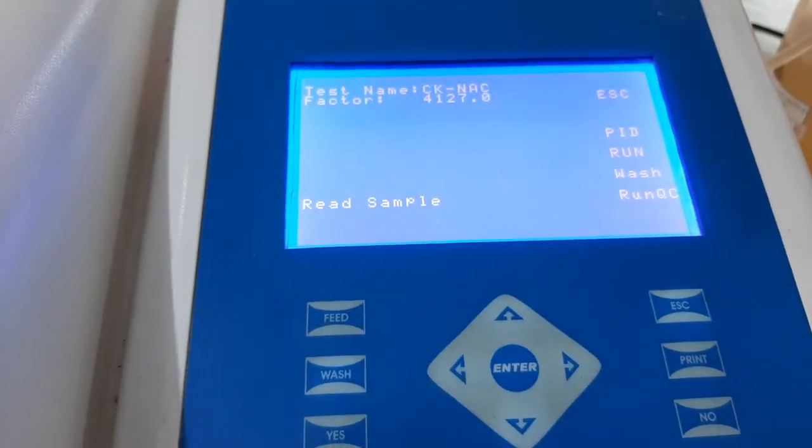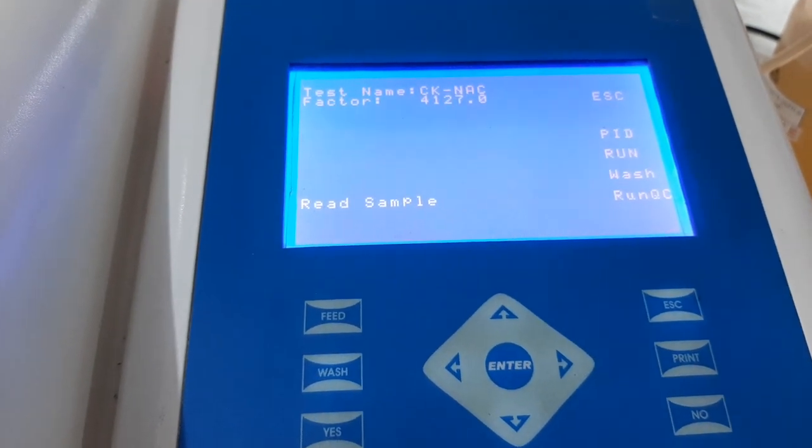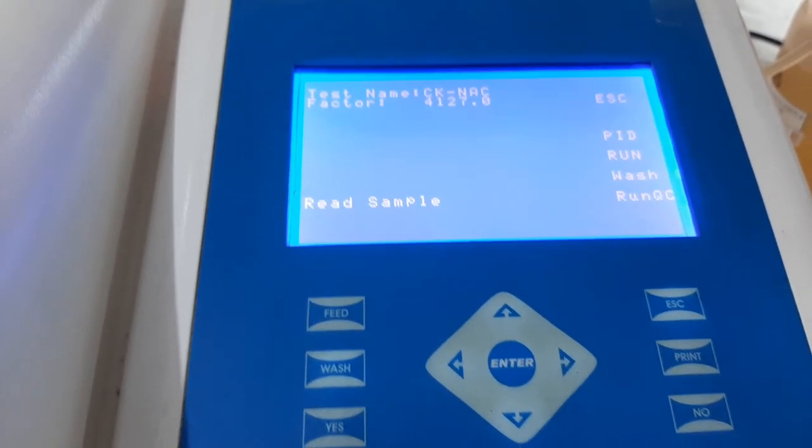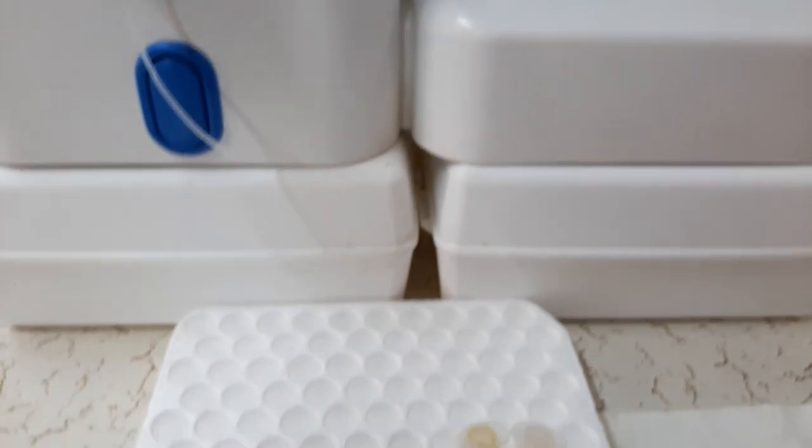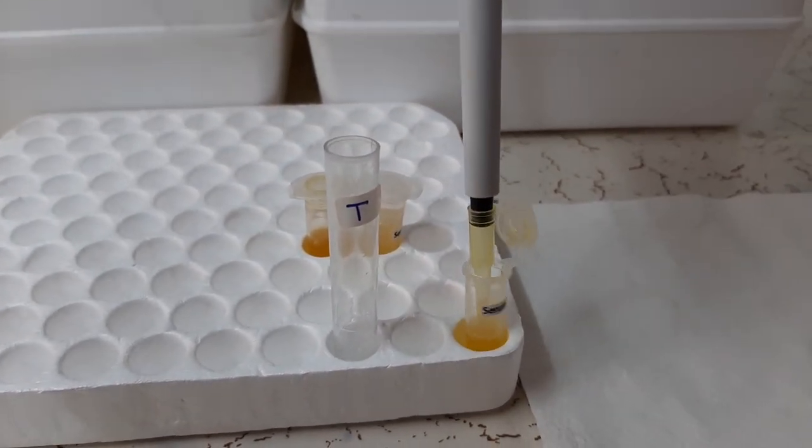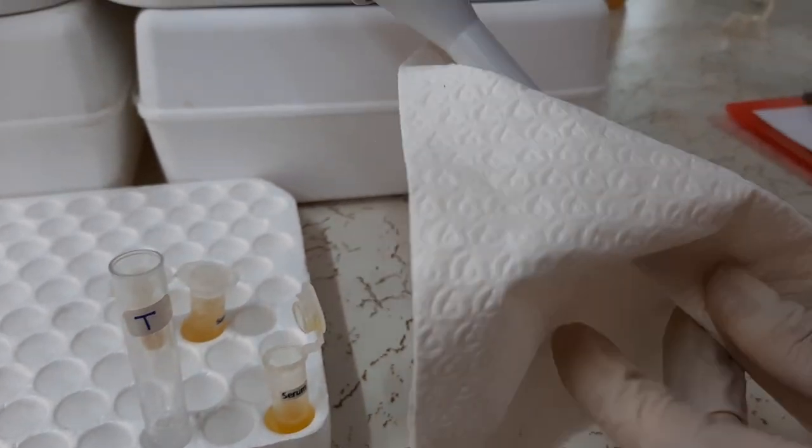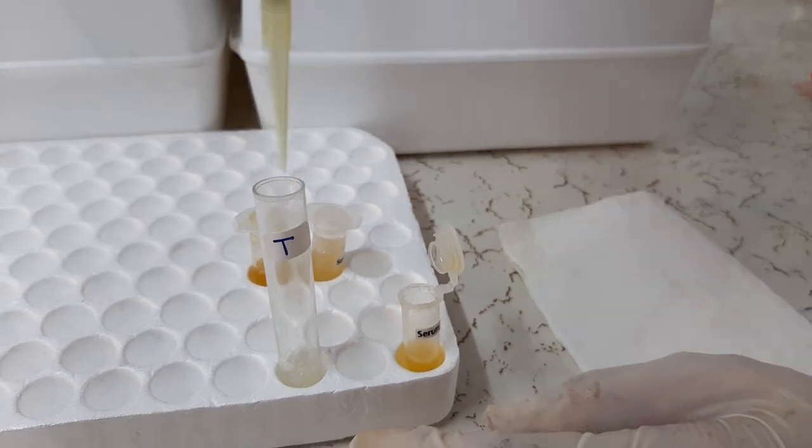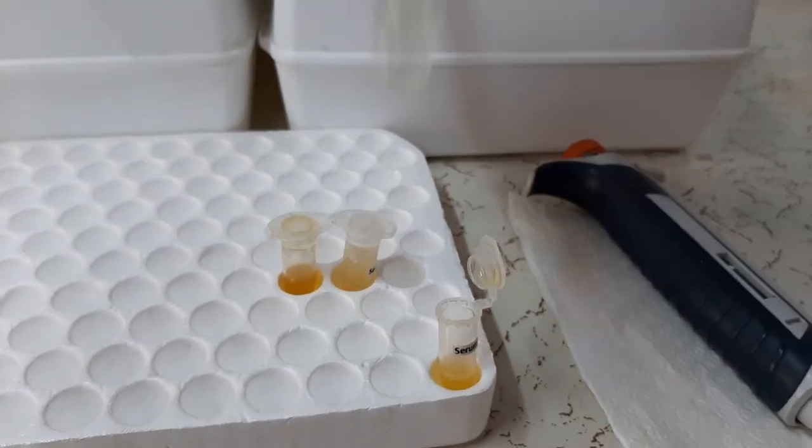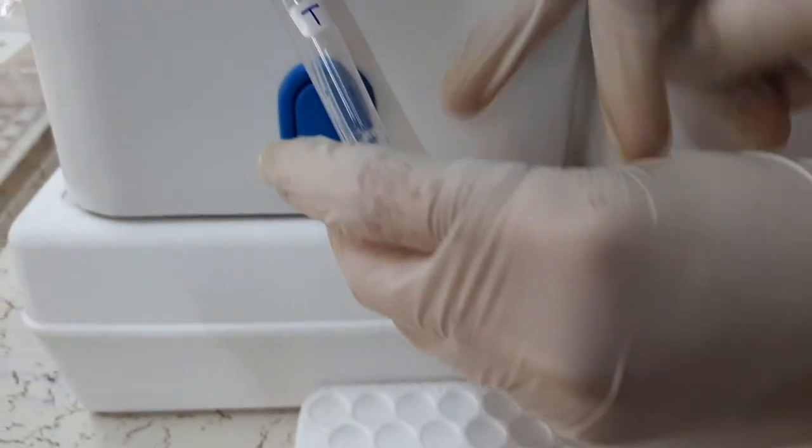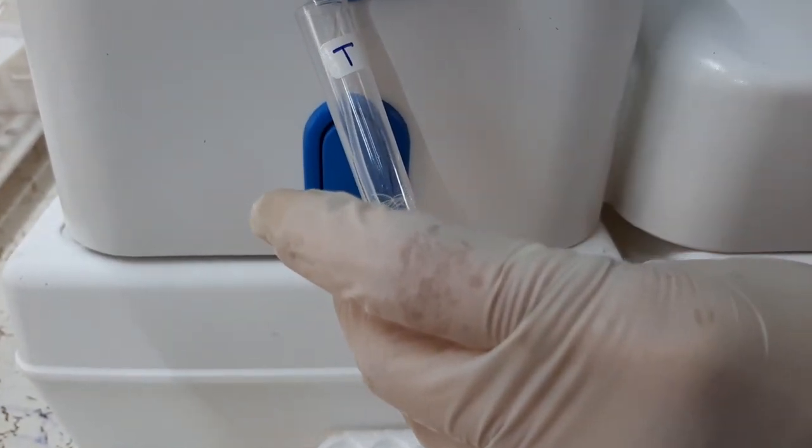So now what we need to do is add the sample as the program is giving the message to read the sample. To do this, we will aspirate 40 microliters of patient sample and then wipe the outside of the tip using tissue paper. And add the sample into the working solution previously prepared. Mix it well and then aspirate the reaction mixture into the flow cell.